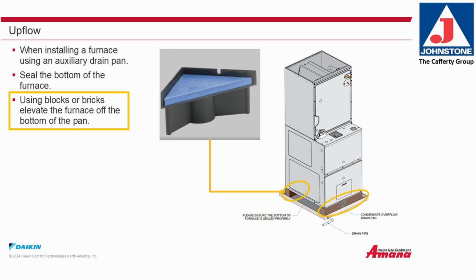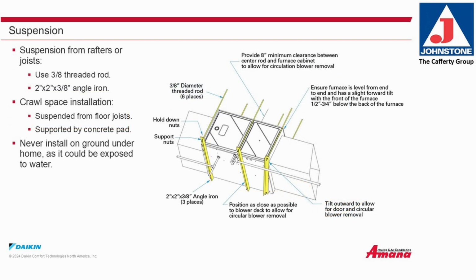Use blocks or bricks to elevate the furnace off of the bottom of the pan. Suspension. Suspension from rafters or joists. Use 3/8-inch threaded rod, 2 by 2 by 3/8 angle iron. Crawlspace installation. Suspend from floor joists, supported by a concrete pad. Never install on the ground under a home. It could be exposed to water.